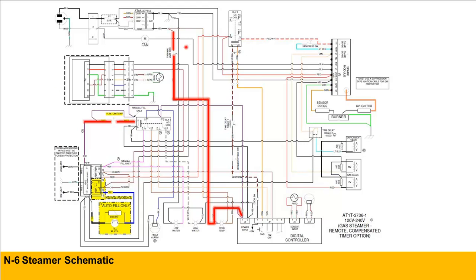And in the wiring diagram, I've actually highlighted the wiring in red. So as Dan showed previously, we have our high water switch. Now the high water switch is being controlled by a float ball, which is located inside the cooking chamber, and inside that float ball there's a magnet. So the switch is a magnetic reed switch. For whatever reason, if that switch was to open, whether it actually has a high water condition or there's a problem with the switch itself or a problem with the float ball, this will de-energize the AC relay. Once the AC relay de-energizes, it's going to illuminate your high water light, at the same time sounding the alarm.